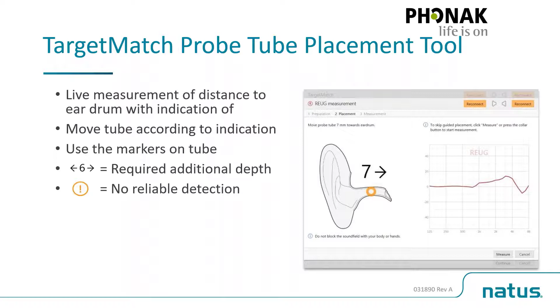So what are you going to see as you do it across the screen? Like I said, if you see the number, that means that you need to push the probe that much further. If you see the green check mark here, that means that you've actually achieved the proper depth. And if you see that orange exclamation mark, that means that something isn't allowing it to measure accurately. That is most common if you're standing right next to the patient or you still have your hand by the patient's ear. You're going to block the sound field and the equipment's not going to be able to make that measurement. I just wanted to highlight that because that really comes up a lot when I'm training. Why am I seeing some of these things?